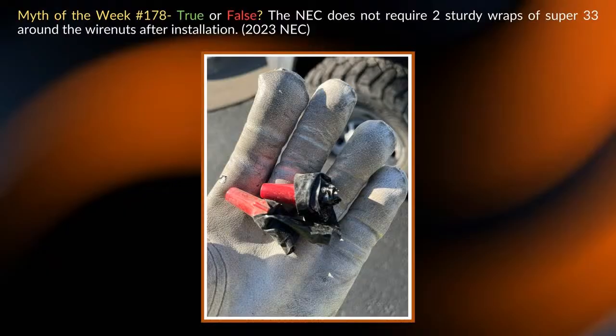Some people argued this makes it more water resistant, and that could be, but wouldn't you use a water resistant wire nut at that point, since that's required? First of all, if you're in a wet location, and plus if you use this tape, it's going to hold moisture inside. True. I was always taught coming up in the apprenticeship that you space the wire nuts up inside the pole, so that if water does get in there, it comes down, crosses over, and drips down, instead of filling up like an upside-down umbrella. But I don't see how the tape would really help that much. I almost think the tape is worse, it would retain moisture versus shield moisture. So we had a lot of really good comments.